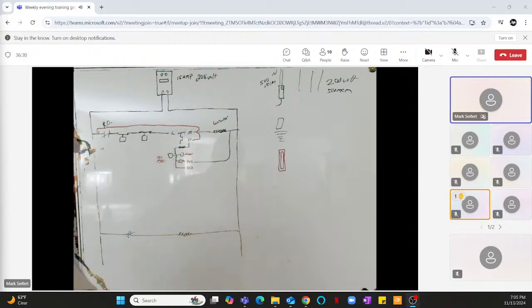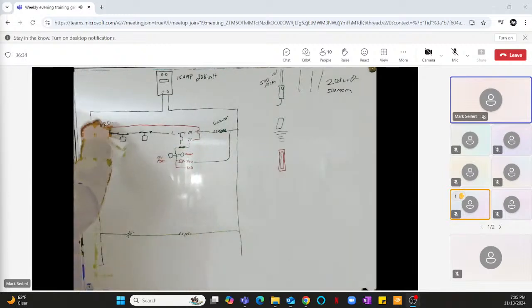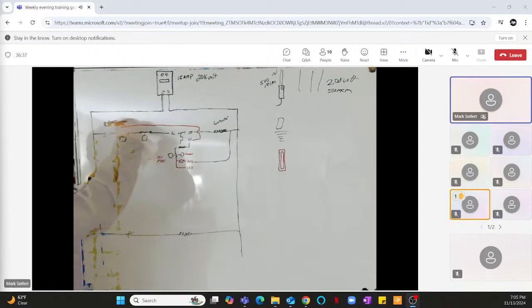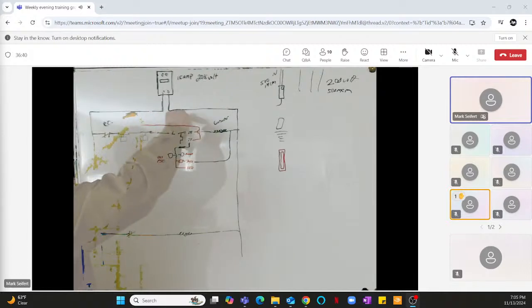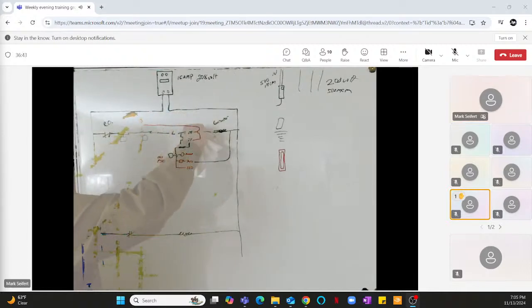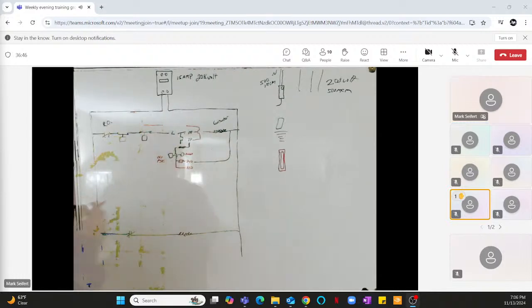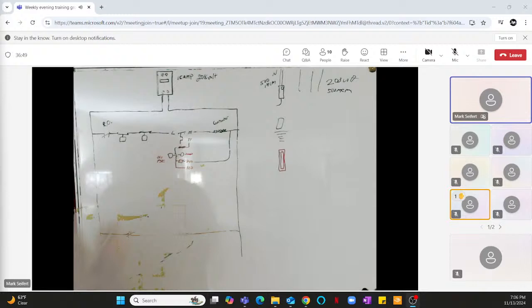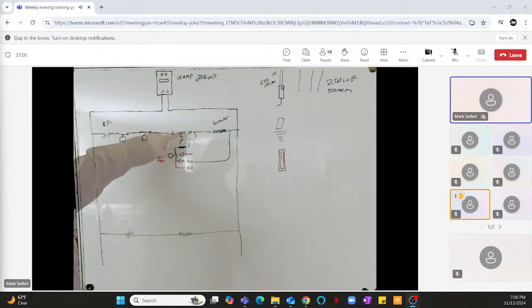Why do we jumper M? I get that question sometimes. Let's go back to a 3-wire. Why do we jumper M? A good question. Glad you asked. Why don't you jumper L? Well, you could jumper L. It wouldn't be a problem, unless this trips. So the reason we jumper M is so that if this does trip, opens this circuit, it kills power to the heater. You don't want this to keep heating up. You want to be able to reset it.